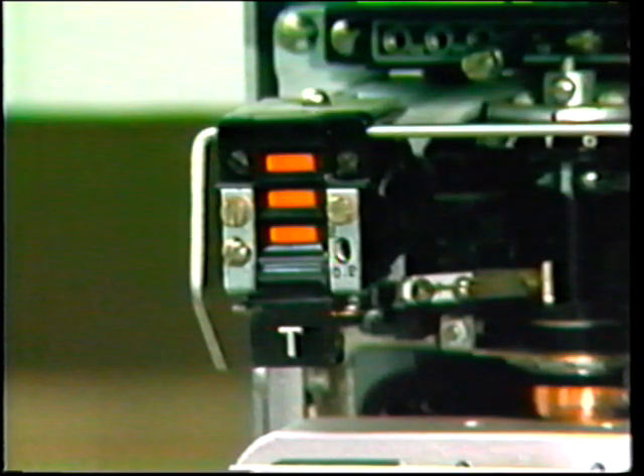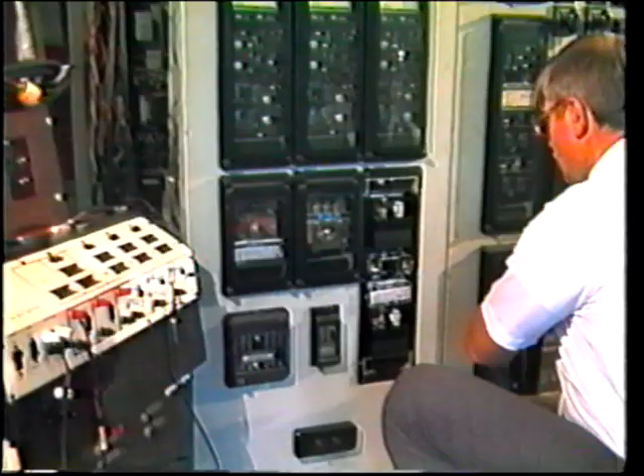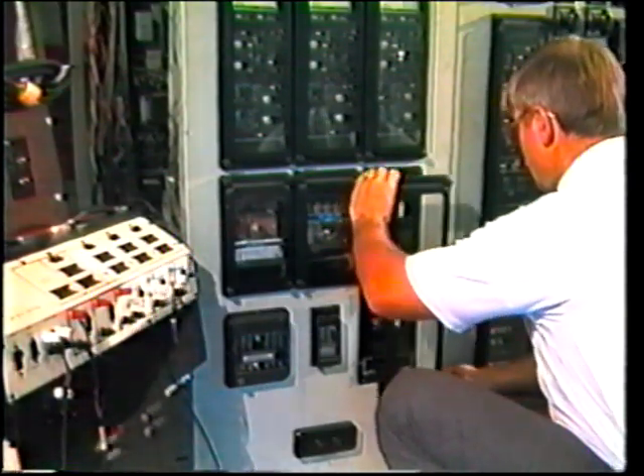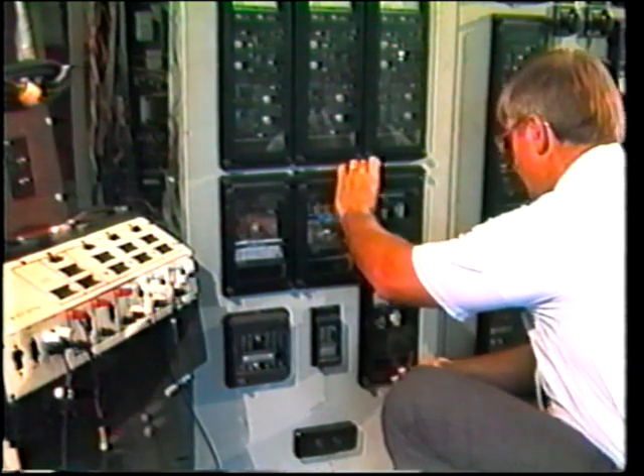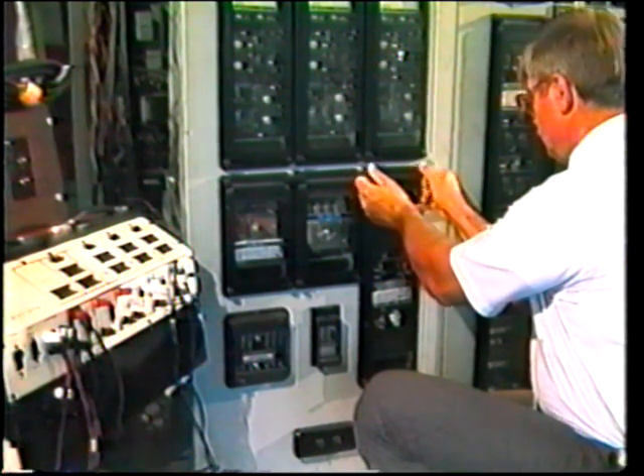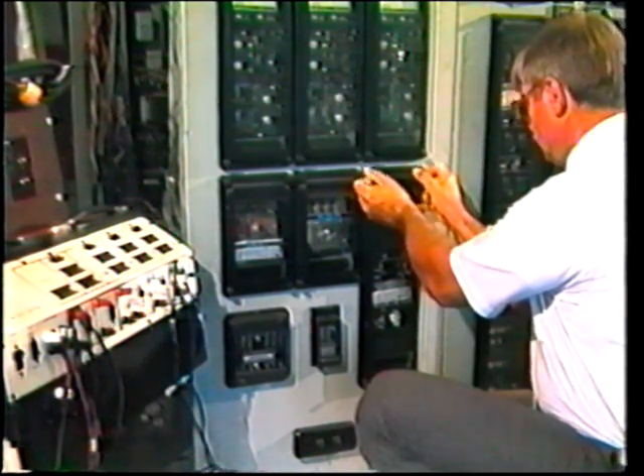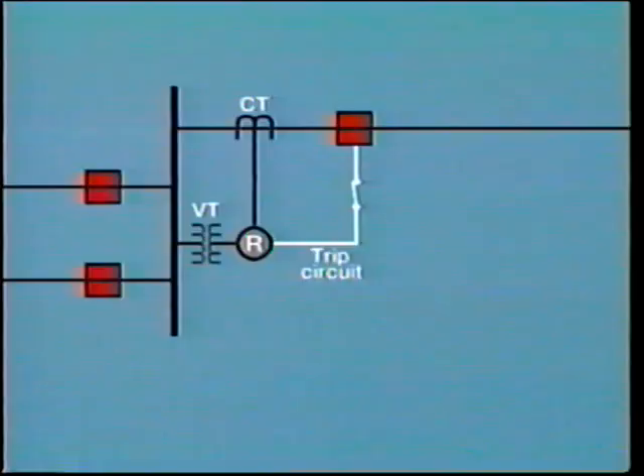Many such incidents have occurred both during installation and removal of covers. I suppose that by now we should have expected that the design of the relay itself would eliminate this problem. But of course, we still have many of these relays out there. Another variation of this problem occurred when the relay cover was not put on properly. It caused the contact to partially close, and then when the cover was removed at the next routine inspection, the slight movement caused the reset lever to bridge and trip the circuit. This problem could have been eliminated by isolating the relay tripping circuits before removing the cover. But this is not always so easy.